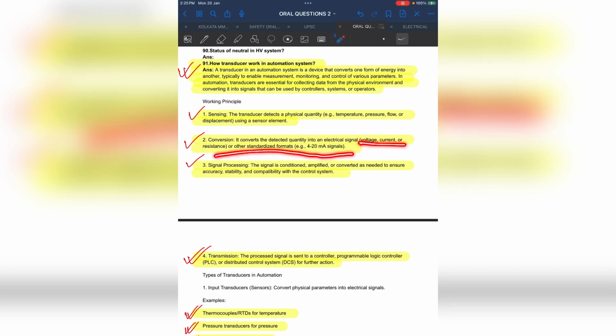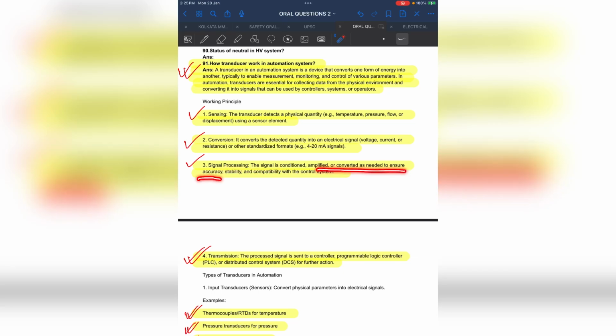After that there is signal processing. The signal is conditioned, amplified and converted as needed to ensure accuracy and stability. And transmission: the processed signal is sent to a controller, a programmable logic controller or distributed control system, for further action, and these parameters can be retrieved by the different PLCs and DCS to do the further actions. If you want to maintain a temperature or a pressure, you first know the temperature and pressure at the field side, then you can take further action based on that.